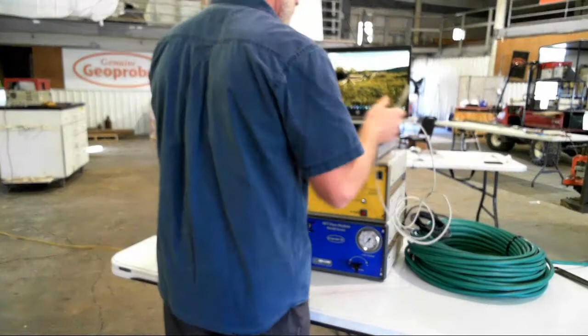Now we will move to the front of the instruments and connect the field laptop to the system. First, we will connect a USB cable from the video USB connection on the interface to the field computer, then connect the data line USB to the computer. There should be 3 new drivers that have loaded onto the computer. To check that they have loaded properly, you can go to the computer's control panel, devices, and printer section. Then we can select the DI acquisition software icon, and it should open in OI-HPT mode.